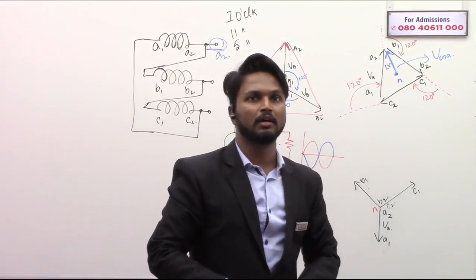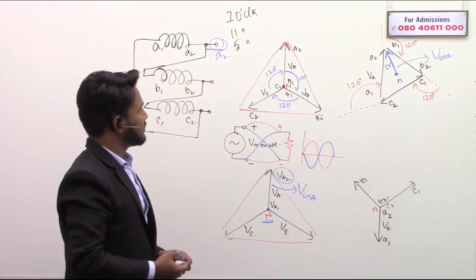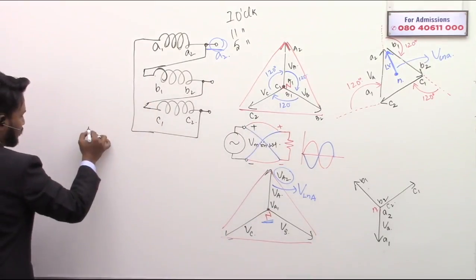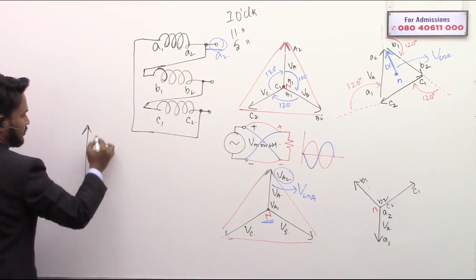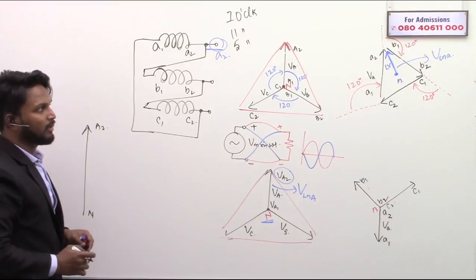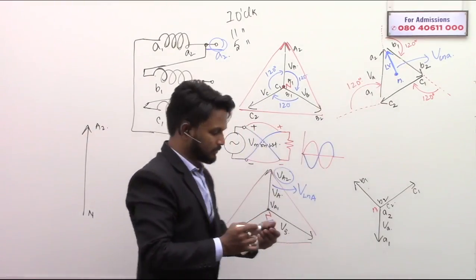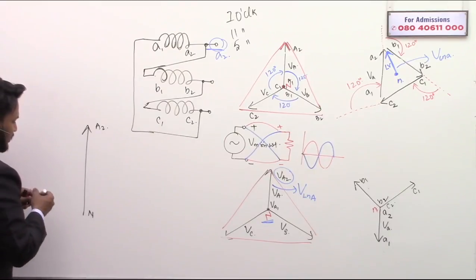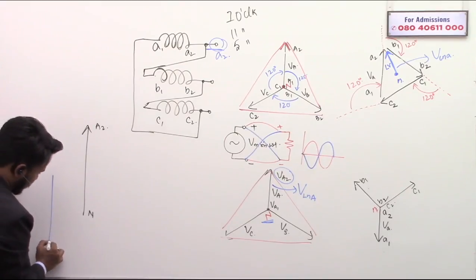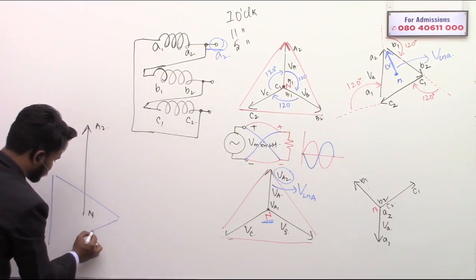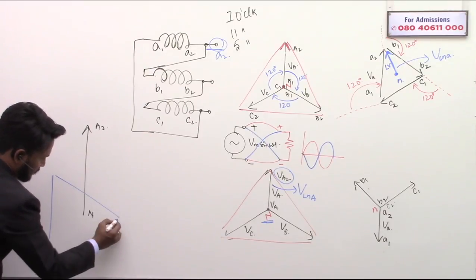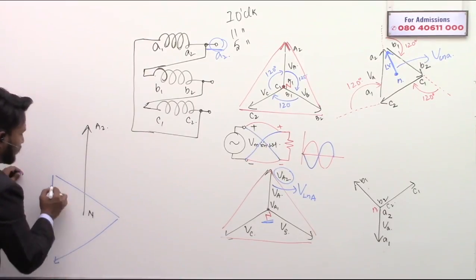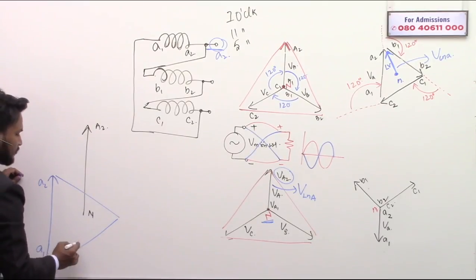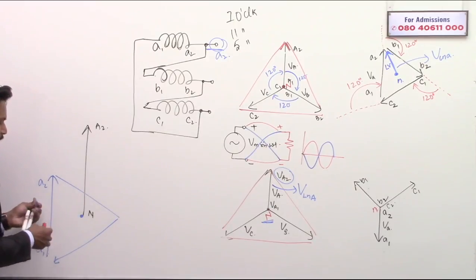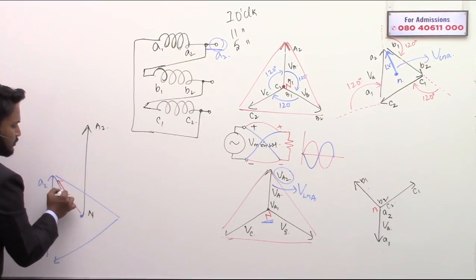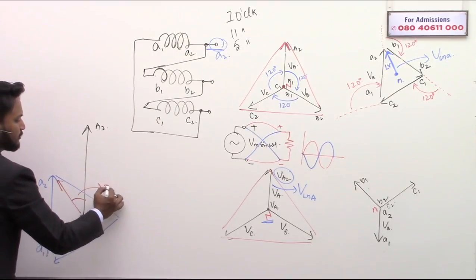Very good, Anjali Kumari and Lakshmi Narasimhan. It is 30 degrees. See here, neutral to line on the HV side is completely erect, and neutral to line on the LV side -- I'm drawing the LV side triangle here. The triangle on the LV side is something like this. This is A2, this is A1, therefore this is neutral. So join line and neutral.